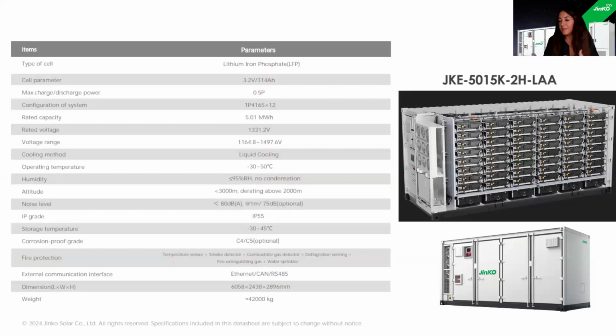So again, for us it's very important that we provide a solution that works if the battery is located close to the sea, close to a desert area, etc. We provide the best solution and adaptation characteristics to increase the lifetime of the battery. Regarding the corrosion-proof grade, the standard is C4, and we can go up to C5 if the battery is close to the sea.